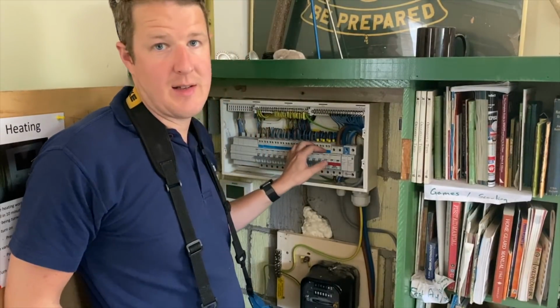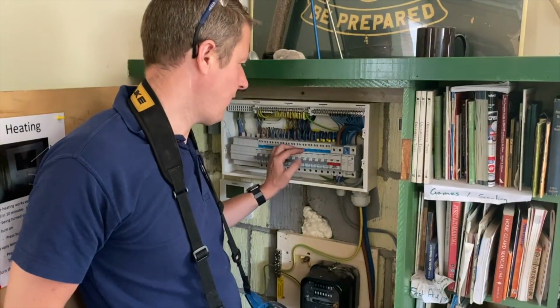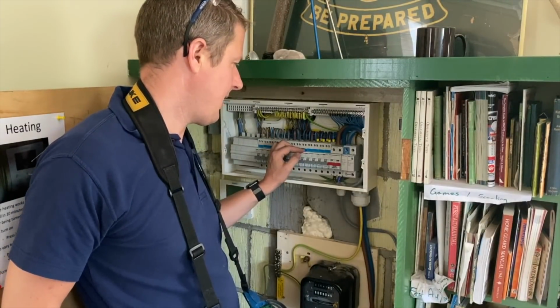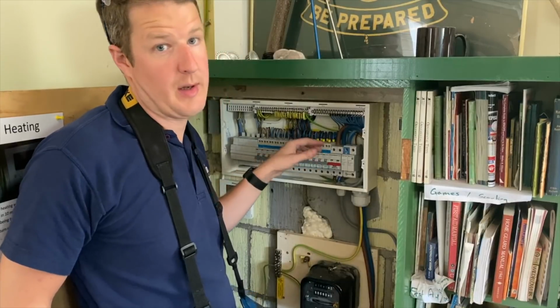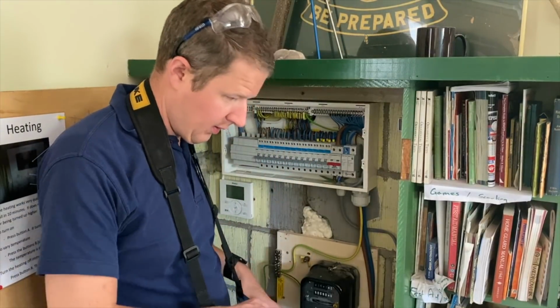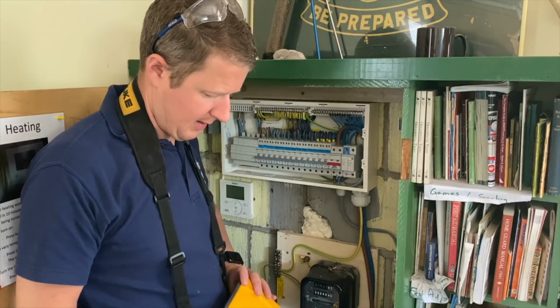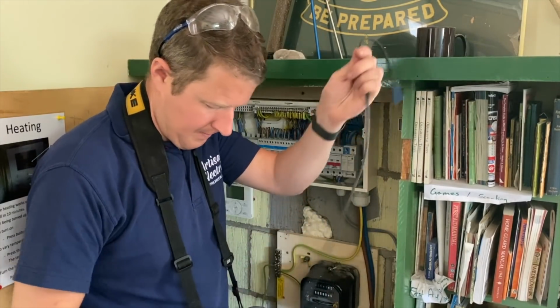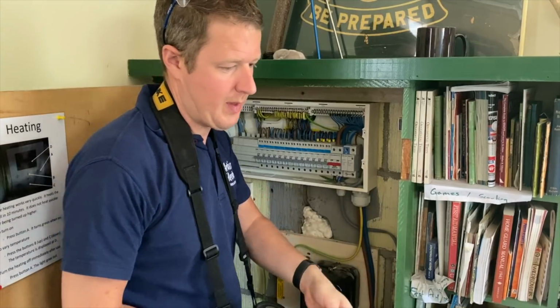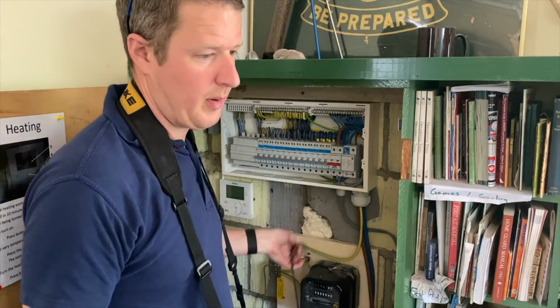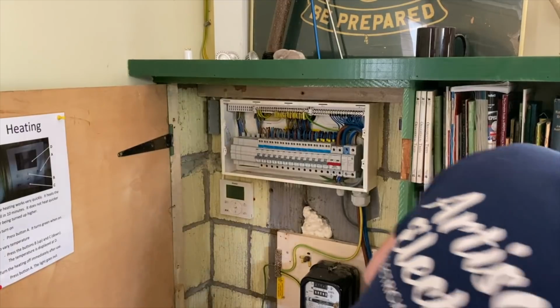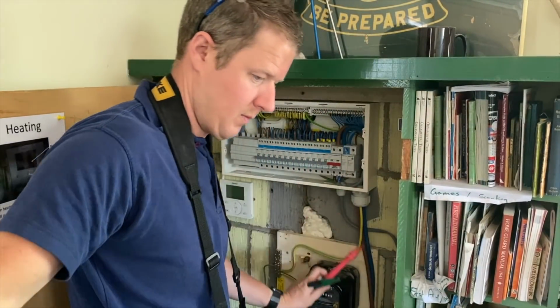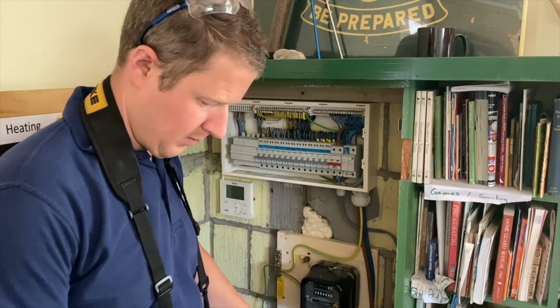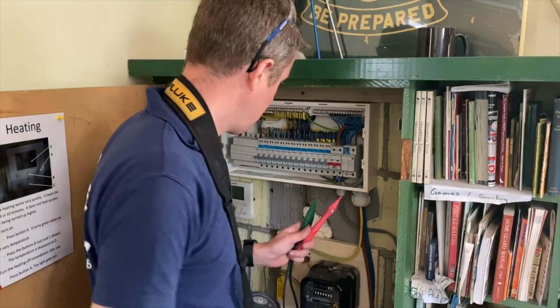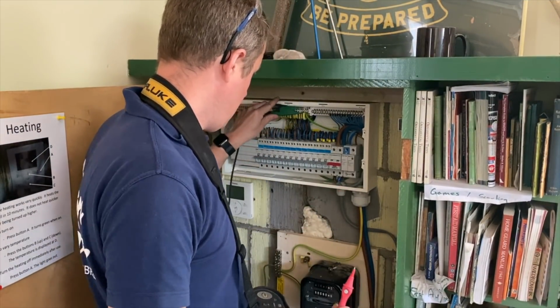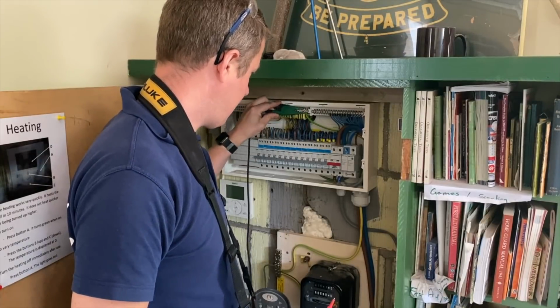Oh, but we need to do RCD testing first, and what I usually do for ease of process, I do the RCD testing here at the board rather than doing it at the end of line and having to run back and forth. So what I'll do first is do the RCD tests on all the circuits, and then once that's done we'll do a fault loop impedance.